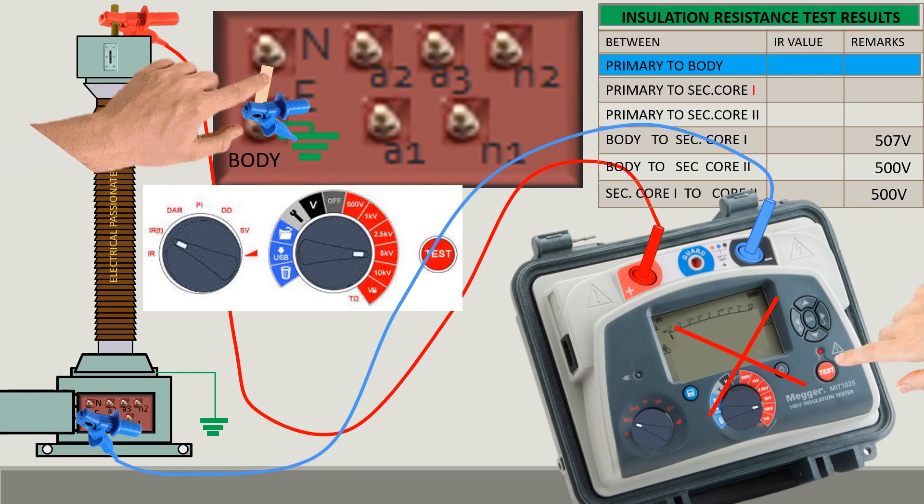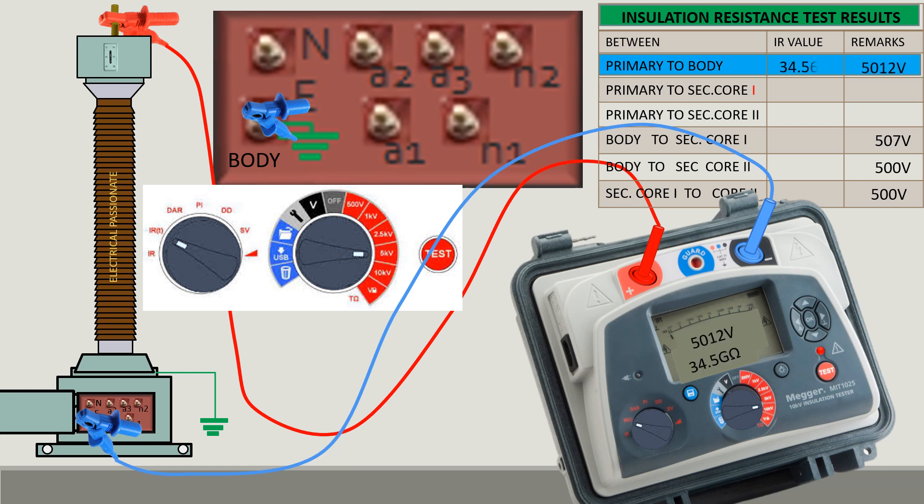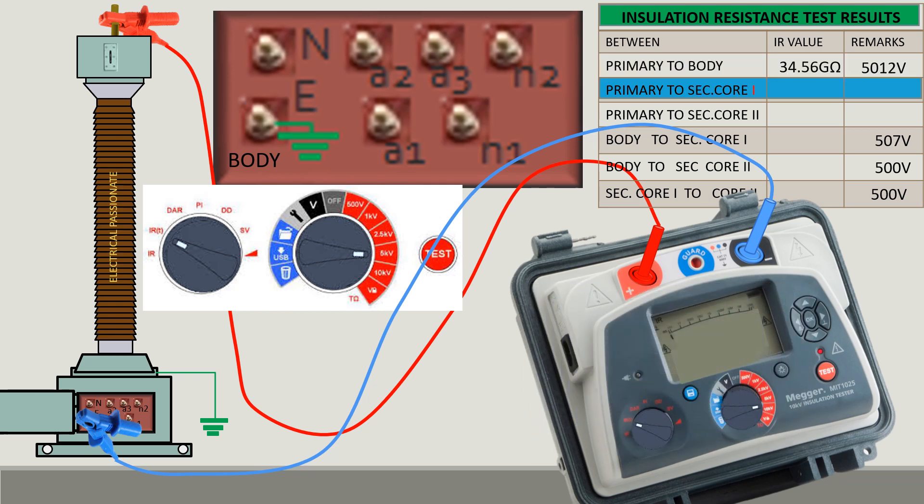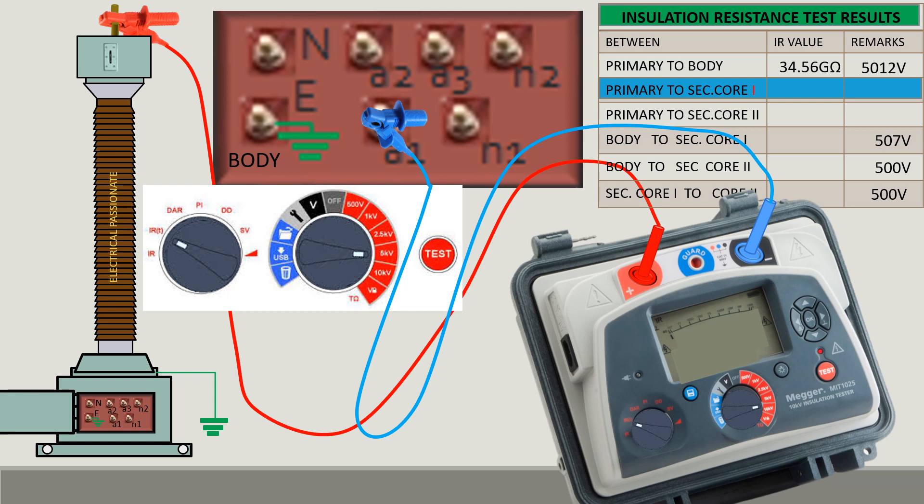Remove the link. Let me show you the numerical. Primary to core 1. Keep the voltage setting at 500 volt for the next tests as these are low voltage winding with lower insulation.